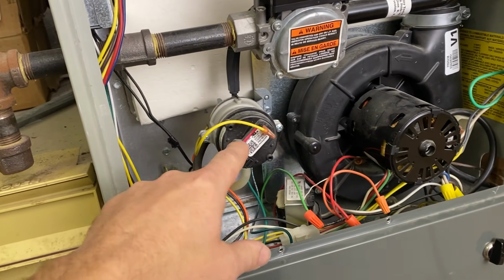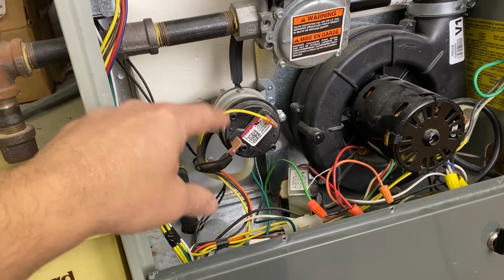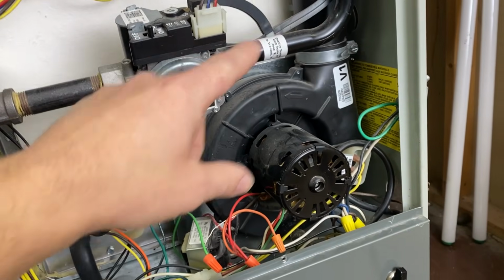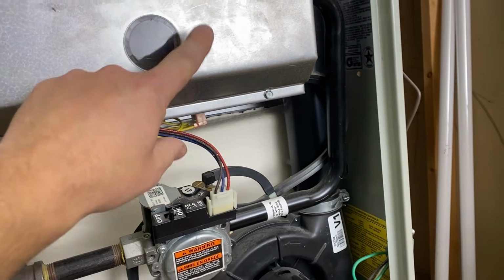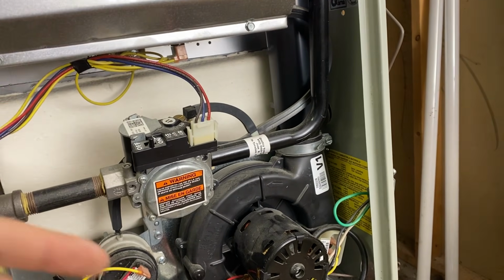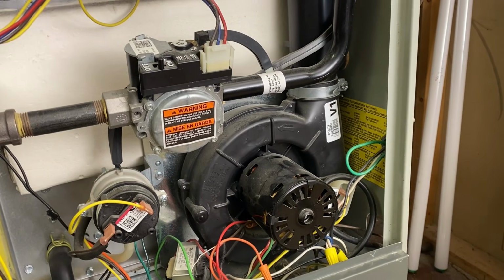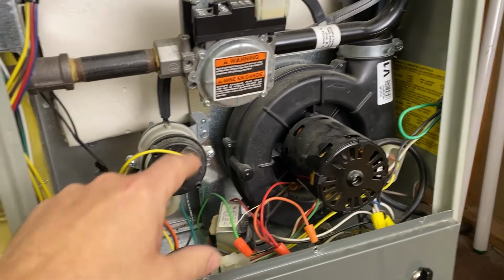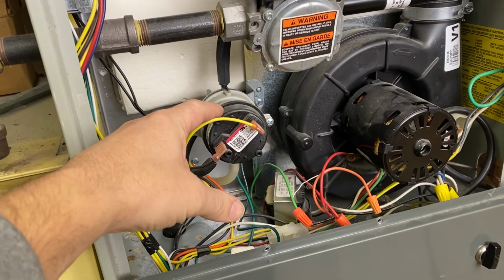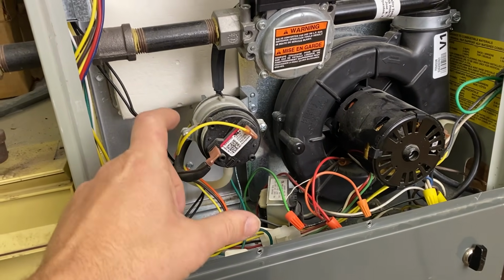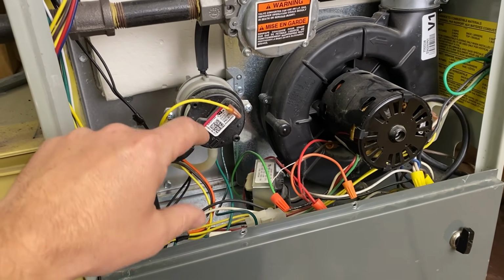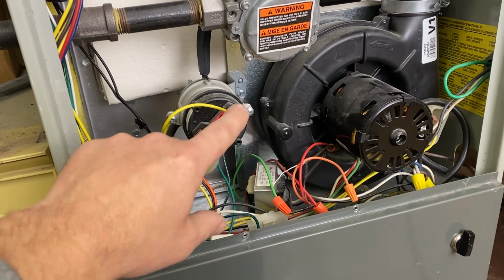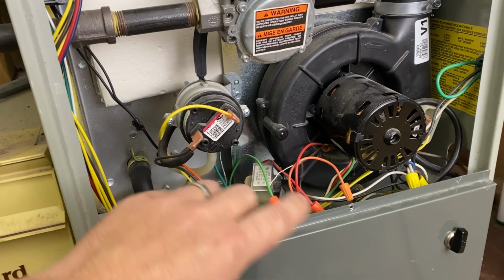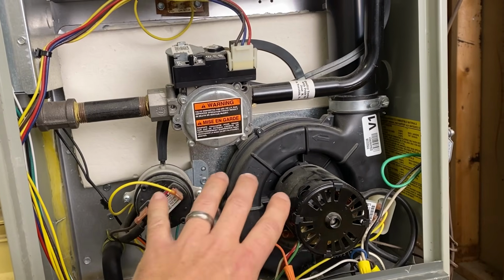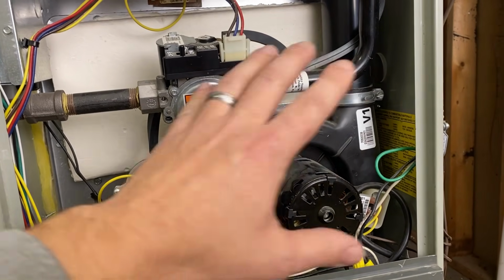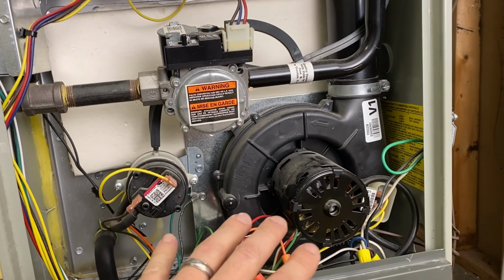Another thing that can go wrong in that process is the pressure sensor that is also in there, and it will sense pressure in the burn chamber. If there's a leak, if there's a hole in the heat exchanger, if there's a clog, if something's backed up or anything like that, this pressure sensor here can also switch. It has a range that it needs to operate in, so that could be a problem also, and that can be something you may need to replace. So if there's a trouble code related to your draft system, those are the major components.